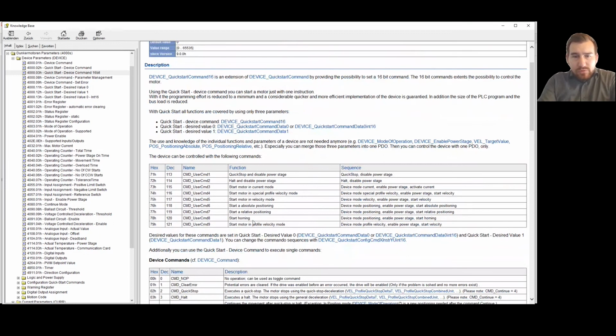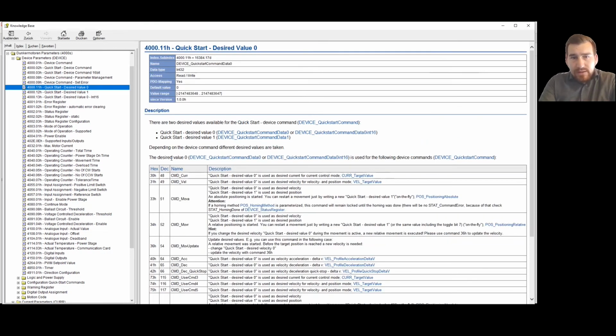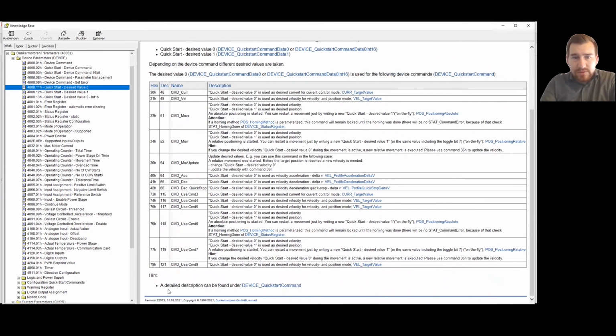Later, we want to start a movement, and therefore we, for example, use the velocity mode, and we can use the command in hex 79. And for this, if we have a look into the 2 other objects, the desired values, here is described for any command which uses the desired value, what the desired value will mean. And in our case, for the command 79, Quickstart desired value 0 is used as desired velocity. So we later will have to use the object desired value 0 as target velocity and then write the 79 into the device command and the motor will move.